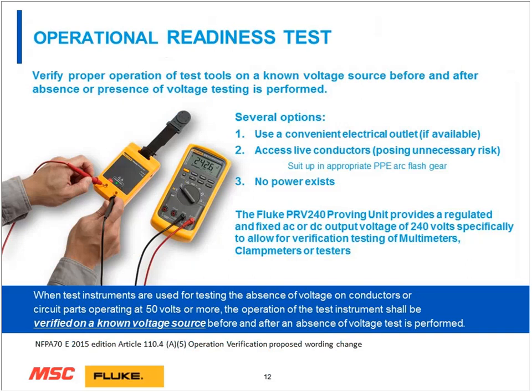Now, just because you've performed a lockout-tagout and you feel that you're safe, you still need to wear PPE appropriate for the panel when you go to that questionable panel. So you need to suit up. You can open the panel at that time, but you need to verify that there is in fact no active voltage on any of the conductors going into that panel. Some could be rewired. Someone may not have mentioned that there's a dual feed in the panel. It may be getting a feed from another circuit or another object.